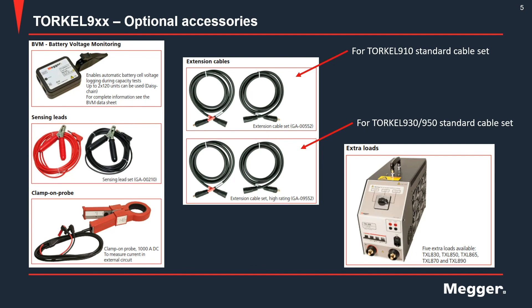Other accessories include BVMs — battery voltage monitors — which are used to monitor individual cell voltages; voltage sensing leads, which are used for more accurate battery voltage measurement by taking the measurement at the battery posts; and the clamp-on probe, which can be used for external current measurement in certain situations, such as when you use extra load units in parallel with the TORKEL. The clamp-on probe measures the total current in the circuit and provides feedback to the TORKEL, which then regulates the current and maintains it at the desired level.